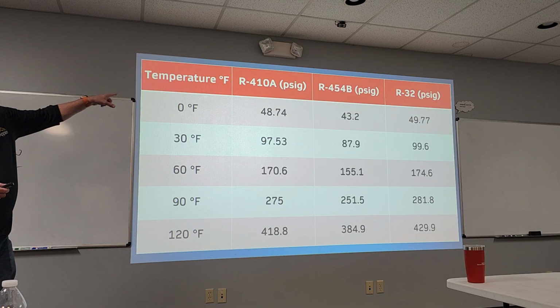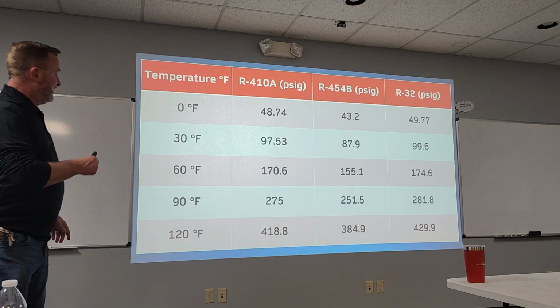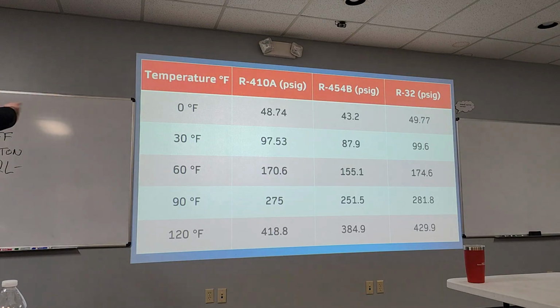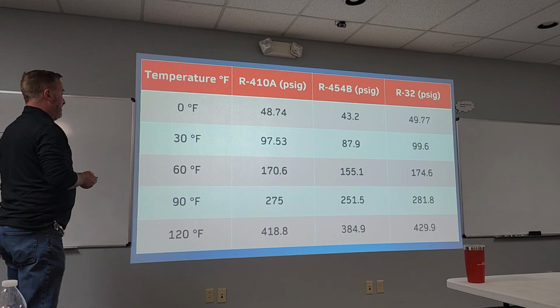This one shows you 410A, 454B, and R32, and as you can see across the board, everything is very similar, not much difference. Whereas when we went from R22 to 410A, you had to get new gauges, the pressures were different, everybody worried about the pressures. So not a big change with these.